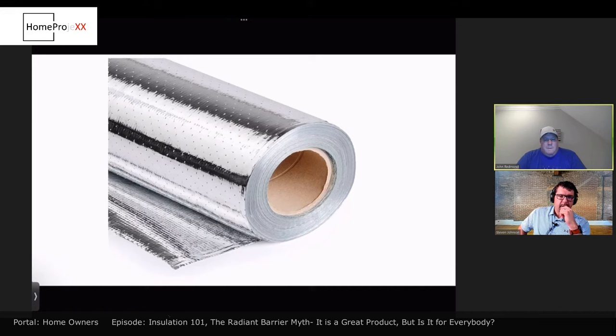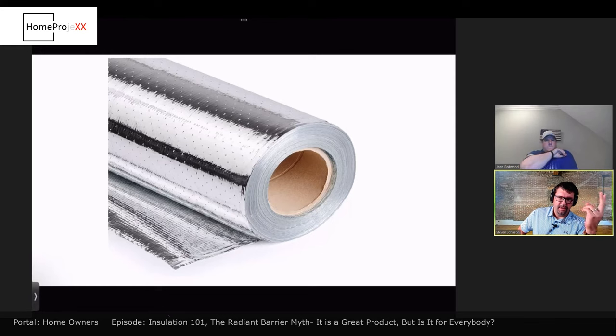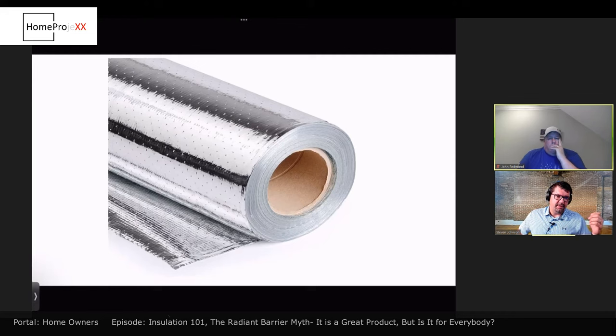What are your thoughts on that, Steve? Well, I have two thoughts. First, the attic ventilation you're talking about has two purposes. One is to evacuate hot or cold air, depending on the season. The other, as we were talking about pressure differentials earlier, is that your eave vent and your ridge vent work in parallel to make sure air flows through your attic, so you don't have a difference in pressure between the outside of your attic and the inside, because your roof under high wind conditions will actually become a wing, W-I-N-G.